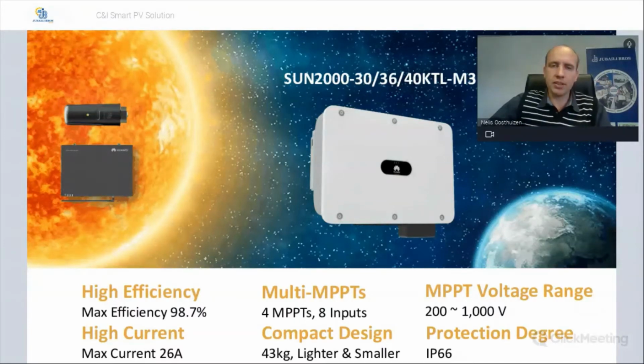The next range of the inverters was the 30 to 40 KTL M3 range, which means it was the third time that this specific range was revised or improved. Efficiency 98.7, maximum current 26 amps. So this is then compatible with high-powered PV modules. 4 MPPTs, which means it can take 8 inputs or 8 strings. Voltage range from 200 to 1000 volts.